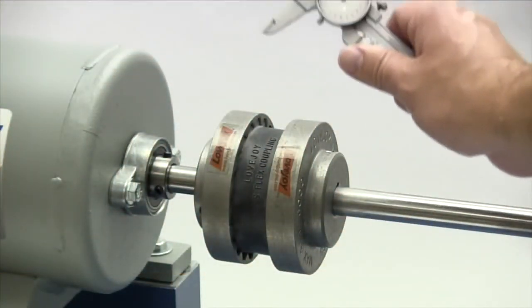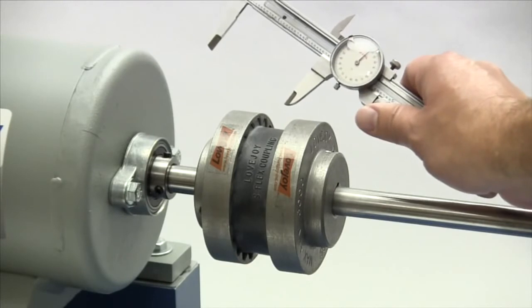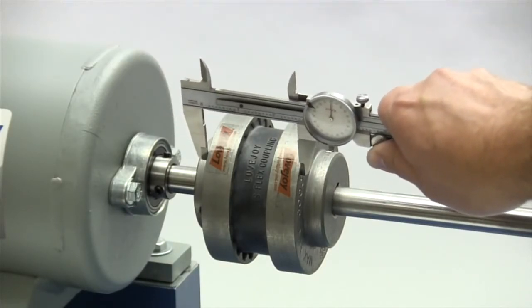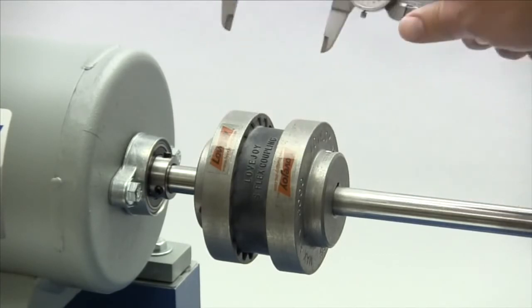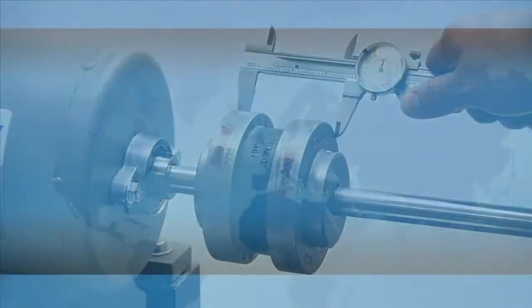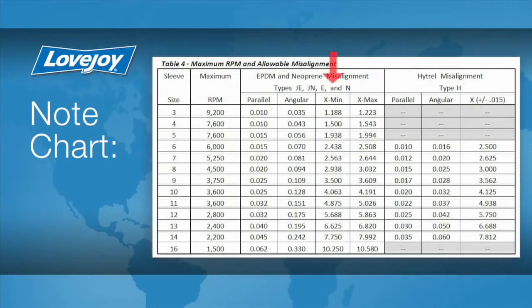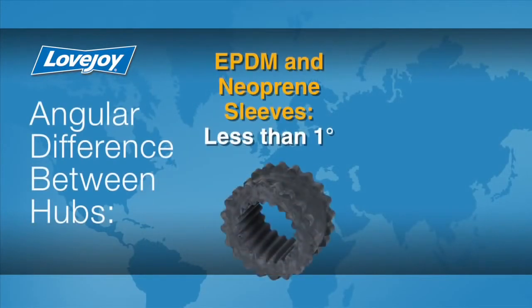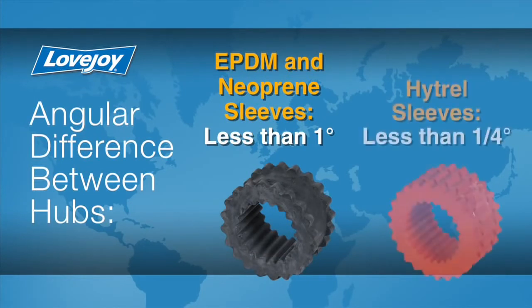Using calipers, measure the distance between the outside faces of the flanges as close as possible to the edge of the flange. It is recommended to take this measurement at four different locations around the coupling: three o'clock, six o'clock, nine o'clock, and twelve o'clock. All of the measurements should fall within the range of Xmin and Xmax on the chart shown here. The maximum difference between any of these measurements should not exceed the value listed in the column labeled Angular. Note that the angular misalignment should not exceed one degree for EPDM and neoprene sleeves or a quarter of a degree for Hytrel sleeves.